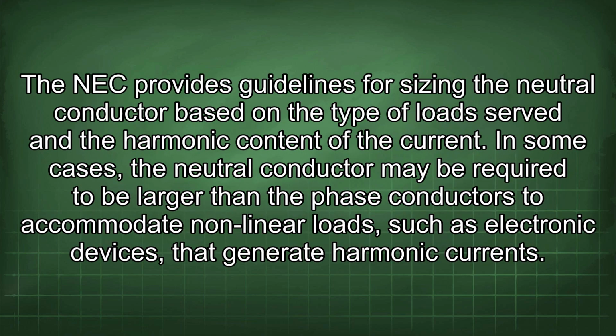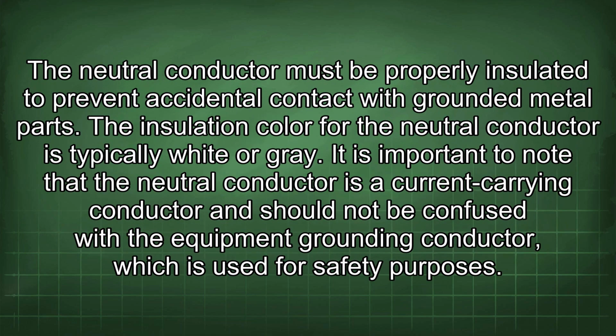The NEC provides guidelines for sizing the neutral conductor based on the type of load served and the harmonic content of the current. In some cases, the neutral conductor may be required to be larger than the phase conductors to accommodate nonlinear loads, such as electronic devices that generate harmonic currents. The neutral conductor must be properly insulated to prevent accidental contact with grounded metal parts. The insulation color for the neutral conductor is typically white or gray.